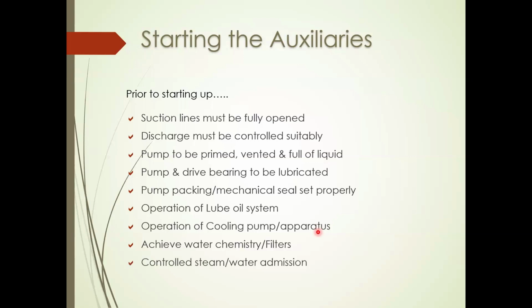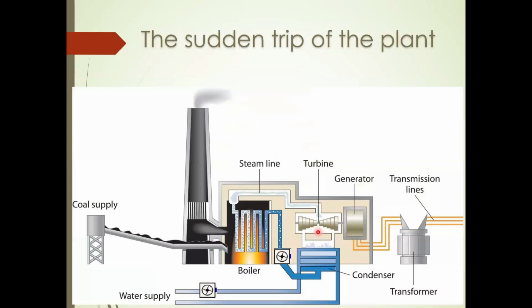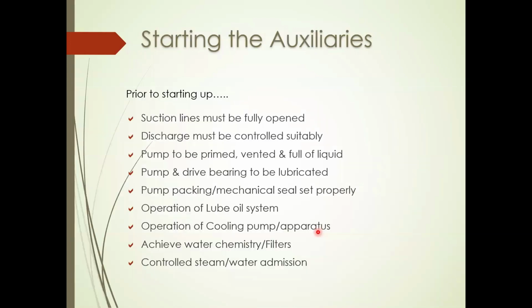And of course, in the case of the steam drum and turbine, you have to control the steam and water admission so that you can control the temperature inside the drum and the turbine, so that there is no uneven expansion. That way you can avoid damage to lines and connections. Now the real issue here is that in reality, there's a long list of items that need to be accomplished before starting up any large equipment.